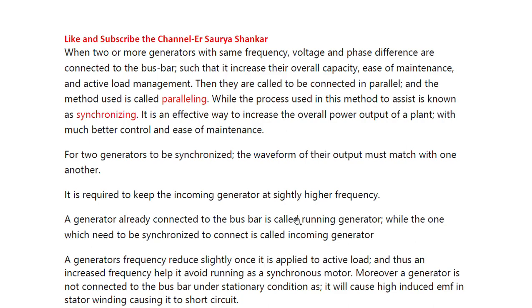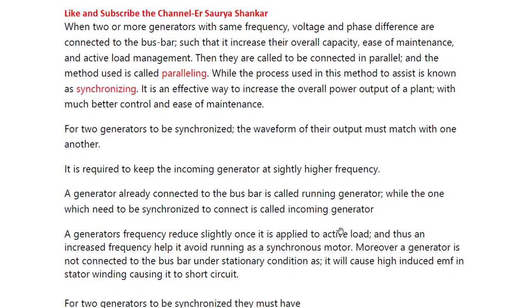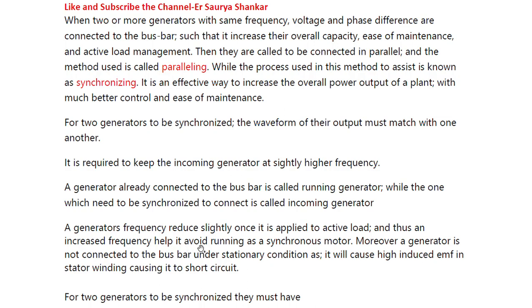A generator already connected to the bus bar is called the running generator, while the one which is to be synchronized and connected is called the incoming generator. The incoming generator is the other generator which we want to take load, which we want to connect with the bus bar — the one we are starting. A generator's frequency reduces slightly once it is applied to active load.